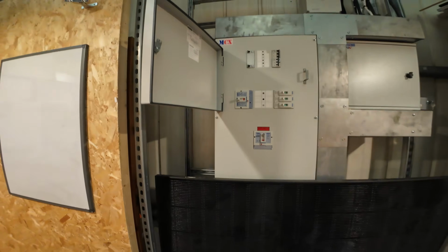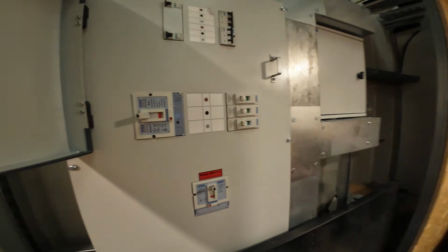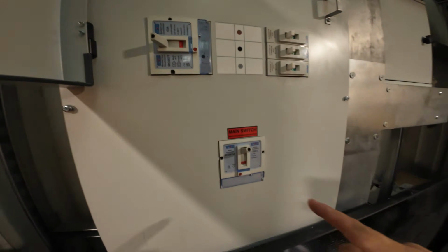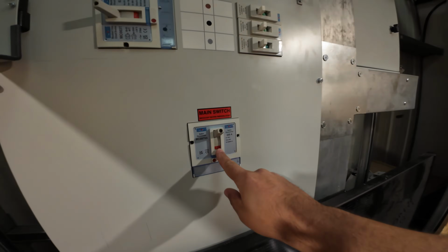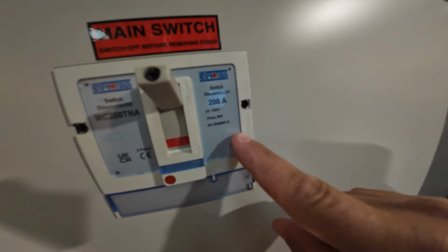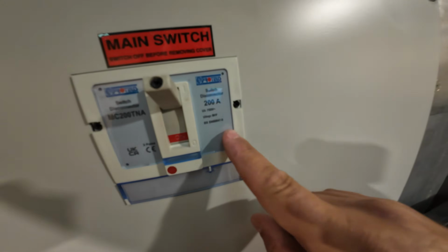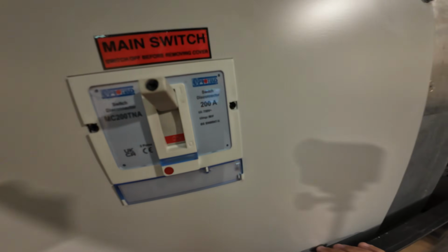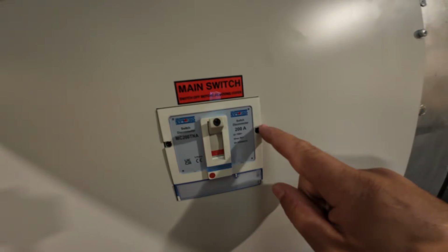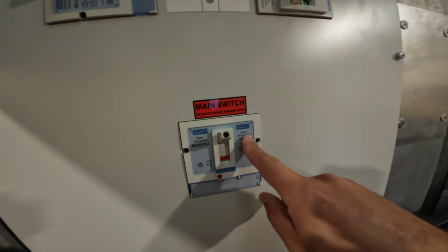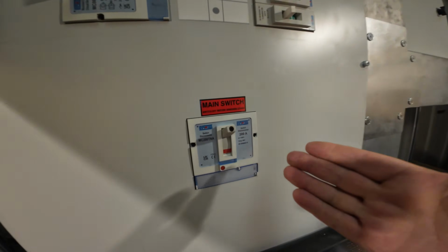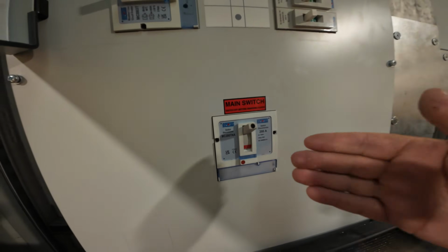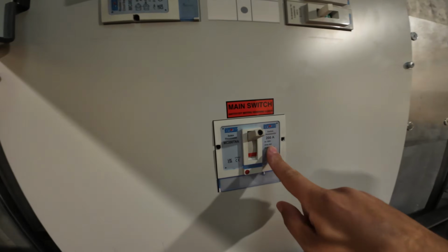However, at the Academy, we are blessed to have lots of switchgear here, all purchased by me, and we can see what we've got. So this here is the main switch disconnector, and you'll see on there its BSEN rating, or product standard, is 60947-3, and that is because it is a switch disconnector. So it's a switch for all intents and purposes, for want of a better explanation. That is the product standard for those.